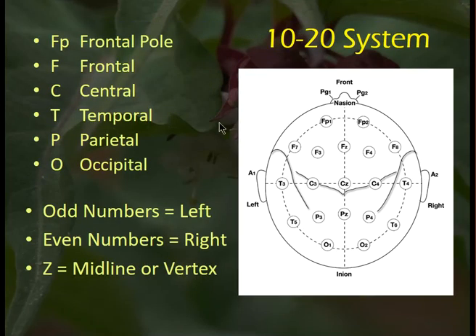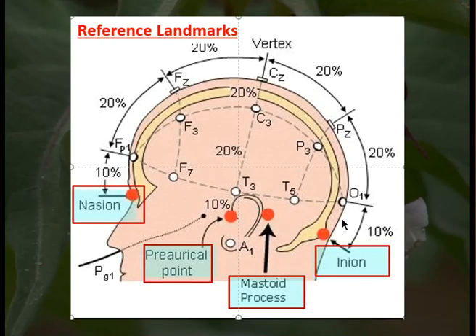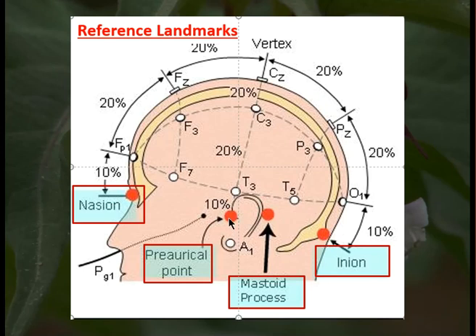The designated coordinate system uses letter-number combinations: frontal pole, frontal, central, parietal, temporal, and occipital. Even numbers are on the right, odd numbers are on the left, and Z indicates the midline or vertex. We measure from the nasion to the inion to get the total distance: 10% up from the nasion is FPZ, 20% further is FZ, and another 20% is CZ — giving us 50% of the total distance. We do the same thing from preauricular point to preauricular point, where 10% up is T3, 20% up is C3, and another 20% is CZ — so 50% of the left-to-right distance is the central midline at CZ.